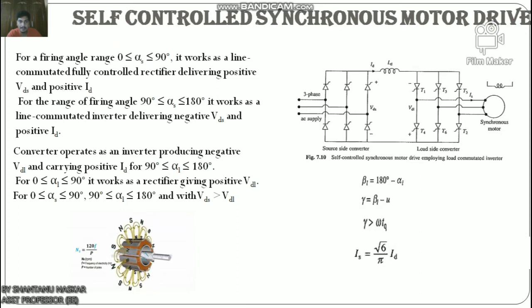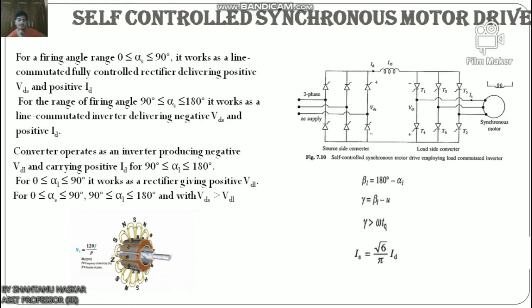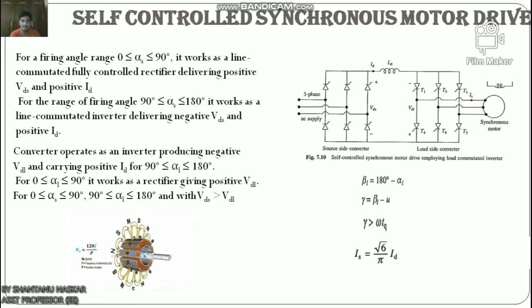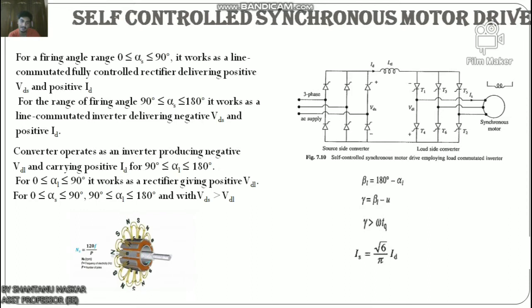The load-side converter and the current source inverter perform essentially the same function; the only difference is that the former uses load commutation and the latter uses force commutation. Load commutation has several advantages: it does not require a commutation circuit, frequency of operation can be higher, and it can operate at power levels beyond the capability of force commutation. The load-side converter performs a function similar to the commutator in a DC machine. The combination of the load-side converter and the self-controlled synchronous motor functions similarly to a DC machine — it is fed from a DC supply, and like a DC machine, the stator and rotor fields remain stationary with respect to each other at all speeds. This drive is therefore known as a commutatorless DC machine.